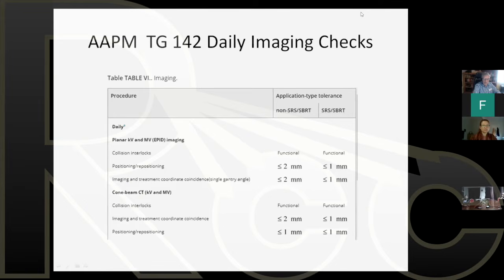Very important is positioning and repositioning. And that means, are the image guidance systems that you're using, either planar KV-KV or cone beam CT or even MV imaging on certain machines, does the positioning guidance software accurately bring you to within 1 millimeter of where you're supposed to be treating if you're using stereotactic radiosurgery?